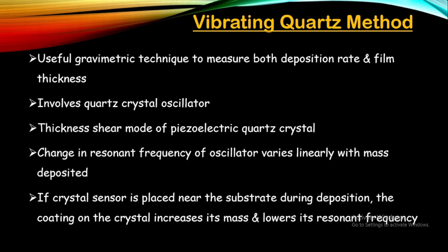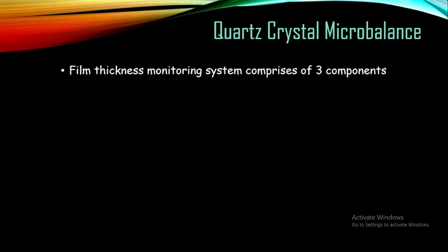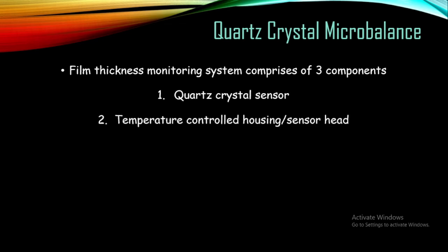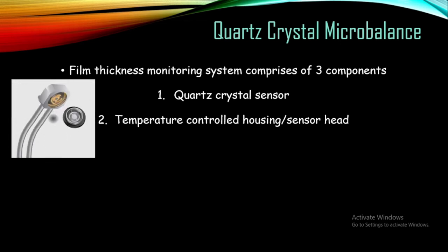We call this system the quartz crystal microbalance, or QCM, or the film thickness monitoring system. It is comprised mainly of three components: first is the quartz crystal sensor, which is the main part; second is the temperature-controlled housing or sensor head; and third is the electronic monitor or controller. The quartz crystal sensor has electrodes acting as contacts and an in-vacuum cable to maintain a proper environment.